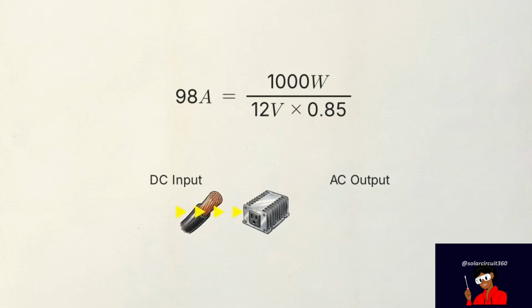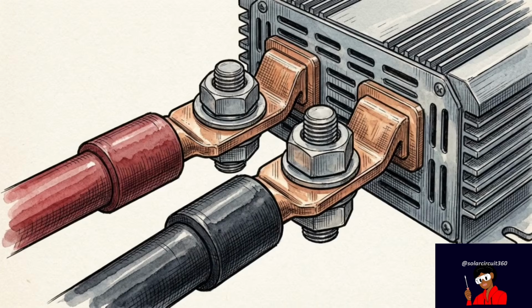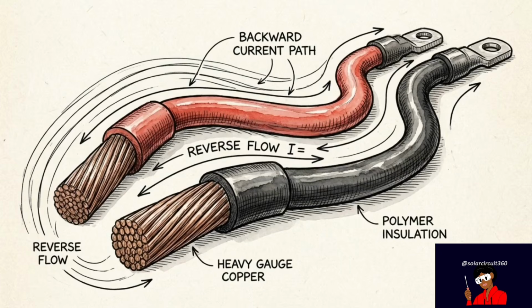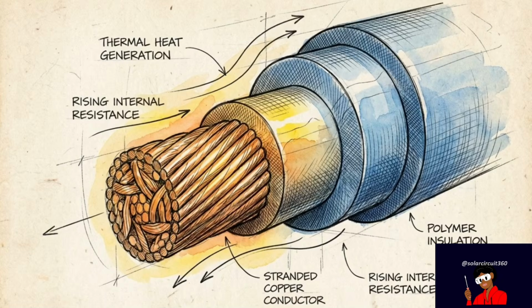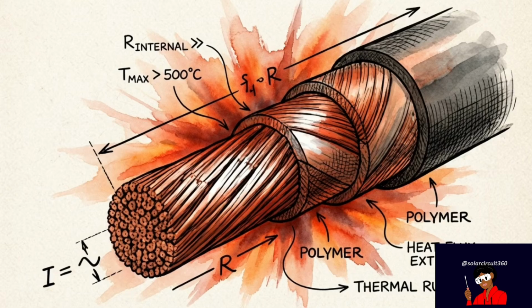Under a continuous load, a 1000-watt AC tool demands nearly 100 amps of steady DC current from the battery to account for conversion losses. When that same tool starts up, the initial 3000-watt surge instantaneously drives the DC demand up to nearly 300 amps. This invisible 300-amp demand is exactly why seemingly capable inverters abruptly shut down the moment a trigger is pulled. The system starves on the DC side. That 300-amp DC surge has to travel physically from the battery to the inverter through your copper cables. Electrical current moving through a conductor generates heat. When you force high amperage through undersized copper, that thermal output increases exponentially due to internal resistance.